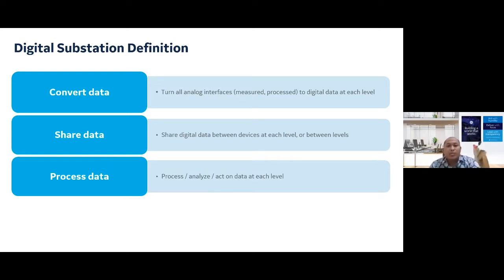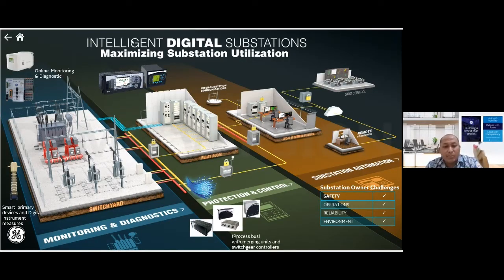So here is the picture showing the digital substation application. The main difference in the digital substation is actually on the side of the sensing of the instrument transformer. As of today, for the conventional substation, the sensing of the current and the voltage still uses the conventional CT and VT. And then from the CT and VT, it is wired up to the relay protection inside the control and protection room.